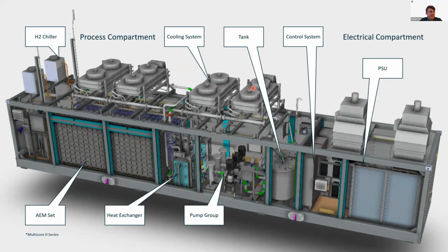So this is not evaluated yet. We can operate on a higher current. So this is basically possible. We shouldn't do this all the time. So we are testing this currently in our prototypes. We don't have the correct time yet, how long you can operate up to 105%. But you can operate at 3%. This is not a problem. As I mentioned, you can shut off the strings individually, and then you can reduce current there, and then you can operate in this area without any problems.